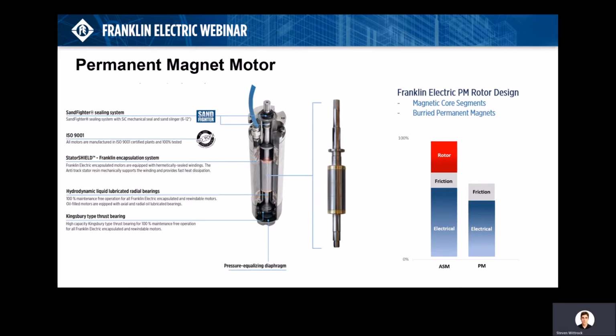If you look at the diagram on the right, you will see the overall electrical and mechanical losses of a submersible motor. If we compare both types of motors, you can easily see that with the PM motor, we have a significant improvement in efficiency, since it does not have any rotor losses. Beside high efficiency, the permanent magnet motor has lower temperature heat rise, and it requires lower amps to run at the same pump load.